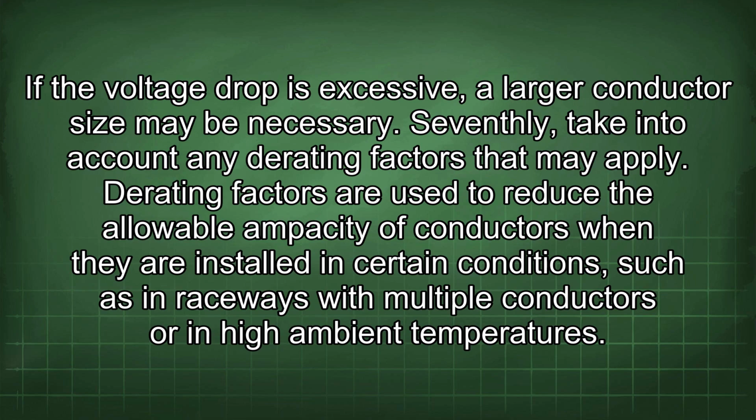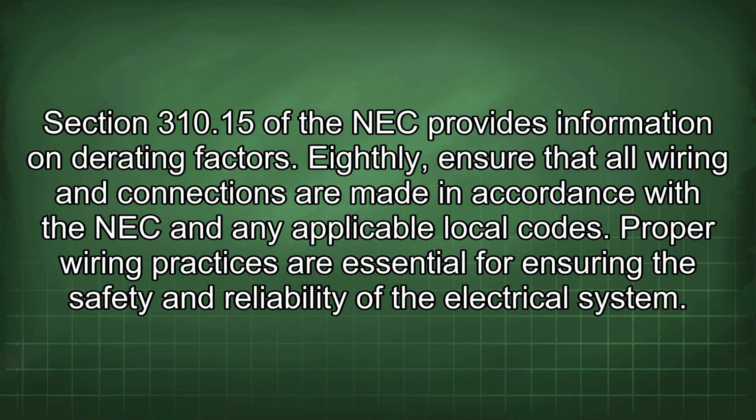Seventhly, take into account any derating factors that may apply. Derating factors are used to reduce the allowable ampacity of conductors when they are installed in certain conditions, such as in raceways with multiple conductors or in high ambient temperatures. Section 310.15 of the NEC provides information on derating factors.